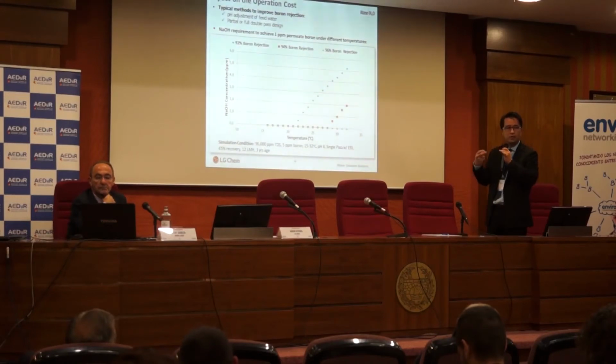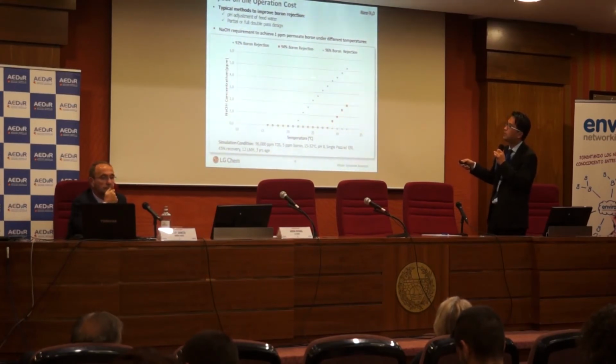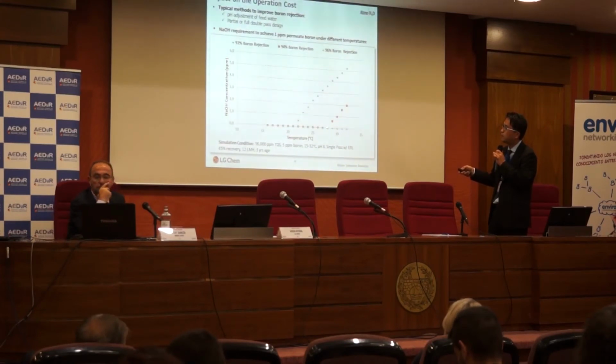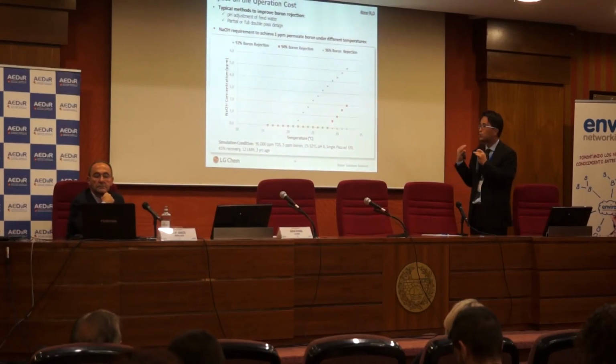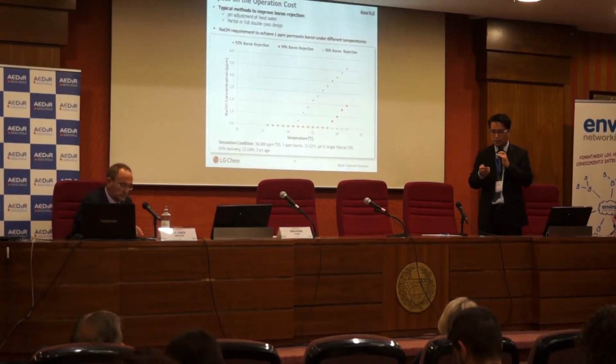For the pH adjustment, you basically need to use caustic, right? This graph shows how much caustic you need to use to adjust the pH to obtain 1 ppm of boron in the permeate. If you have a previous generation membrane, you probably have to use up to 5.2 ppm of caustic to deal with the boron. And with the current membrane we have, you have to add caustic from 28 degrees Celsius and above, and probably up to 2.0 at temperature 32. That is a maximum we assumed for this simulation. But obviously, if you have a future generation 96% membrane, you don't need to add anything.